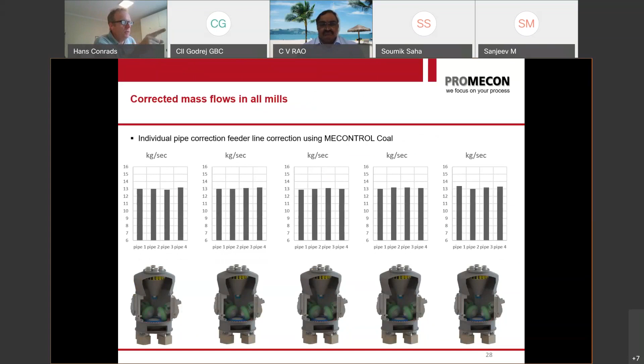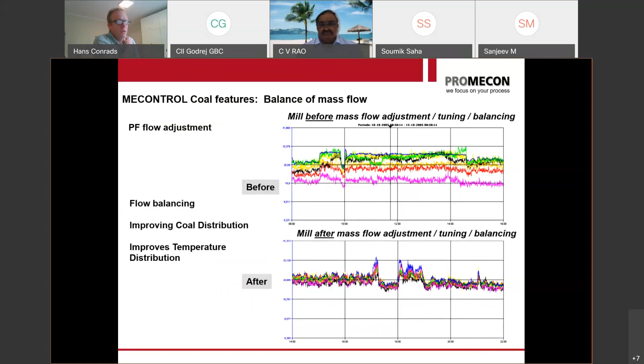This is before, this is after - done at a Danish power station through optimization of coal flow. And this is the impact on NOx: you can come down from 500 milligrams to well below 450, even down to 400 milligrams, just through better burner tuning. This is the best way - you don't need any ammonia, no SCR, no SNCR. It can be done through complete control.